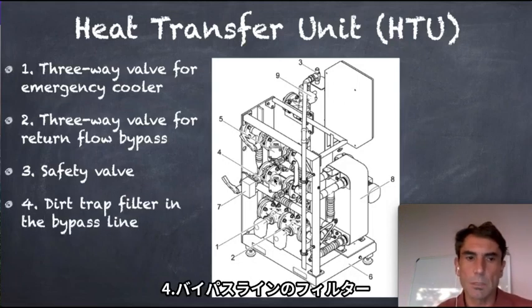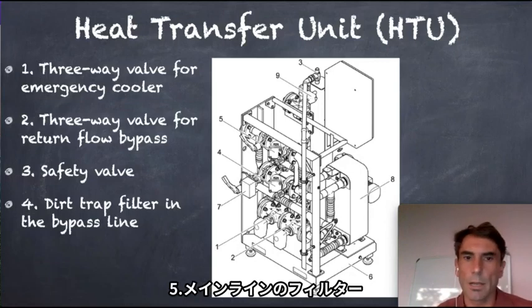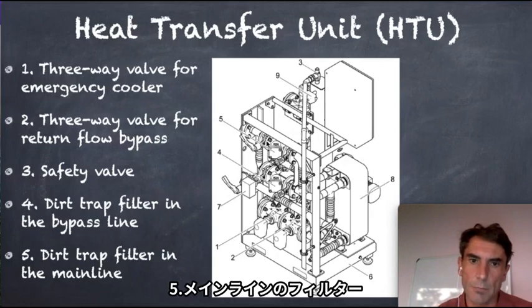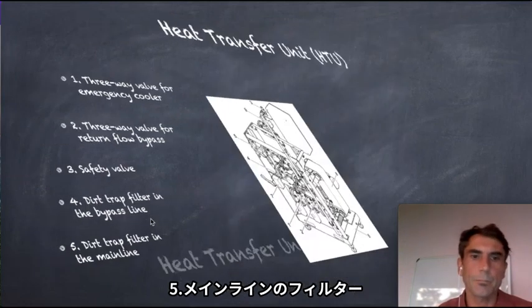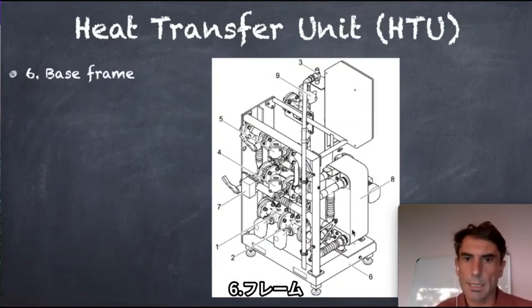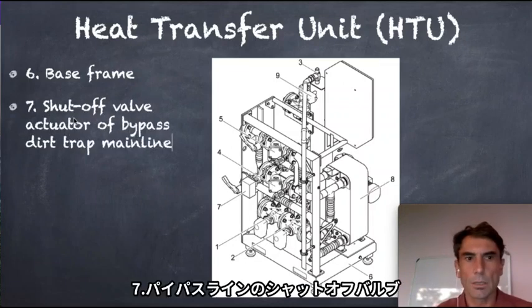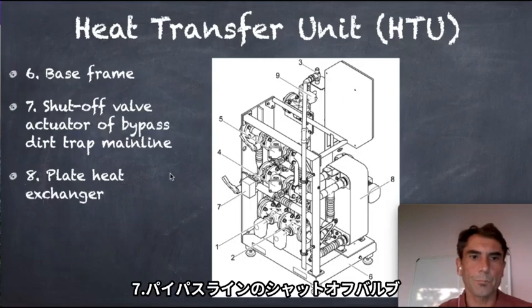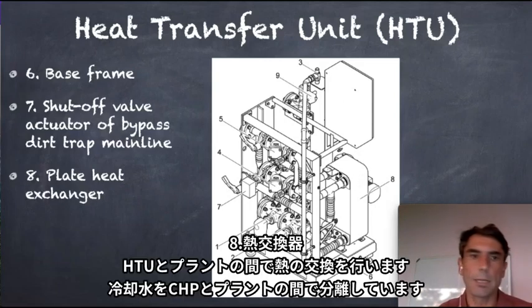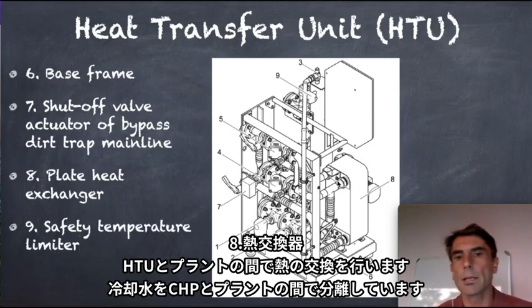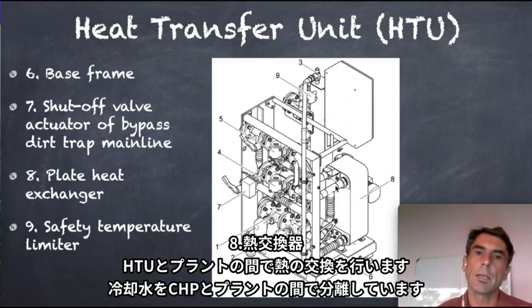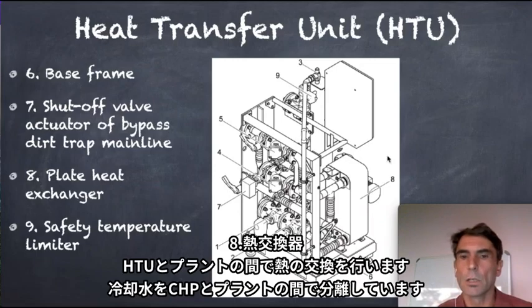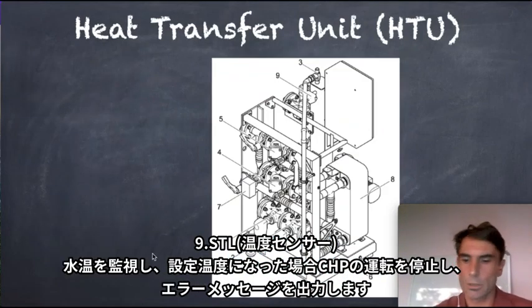Number 4, that's the dirt trap bypass line with a shut-off valve motor. And number 5 is the main line dirt trap, with the main line here and the bypass line here. Number 6 is clear. This is the shut-off valve, number 7, in front of the bypass dirt trap. Number 8 is this big unit here, the plate heat exchanger to transfer heat. It separates the cycle of the HTU and the cycle to the client, to transfer heat from the primary cycle of the CHP to the client side.